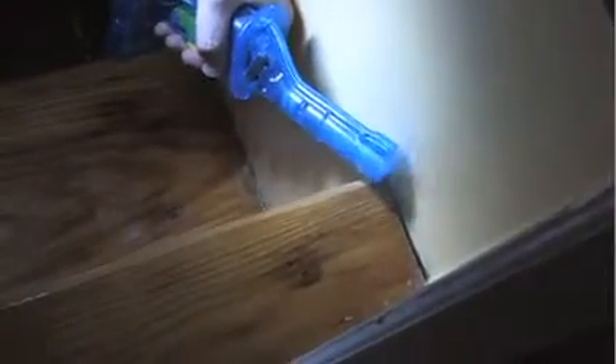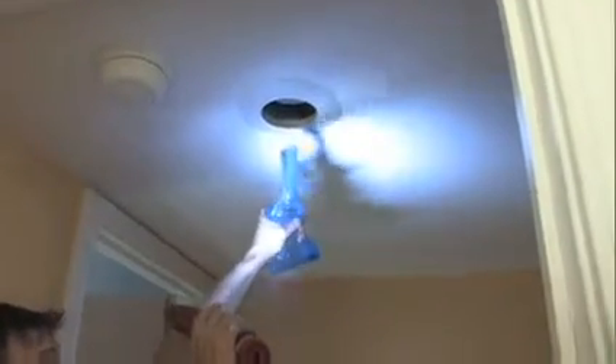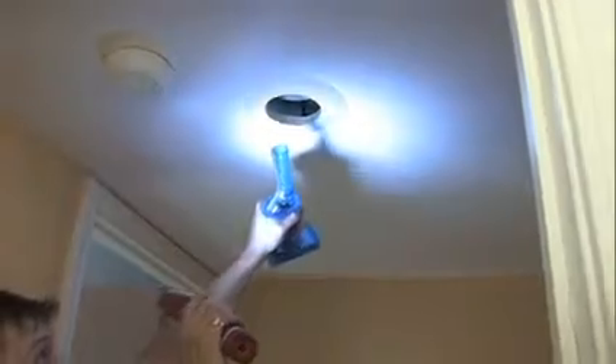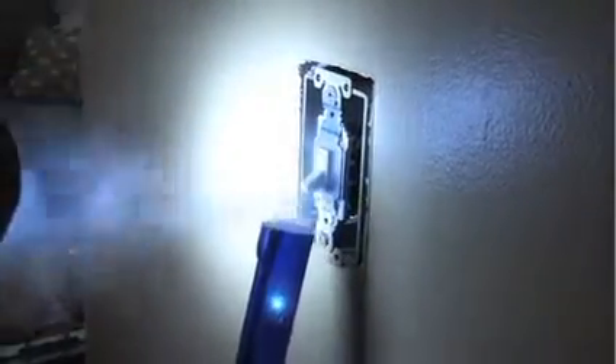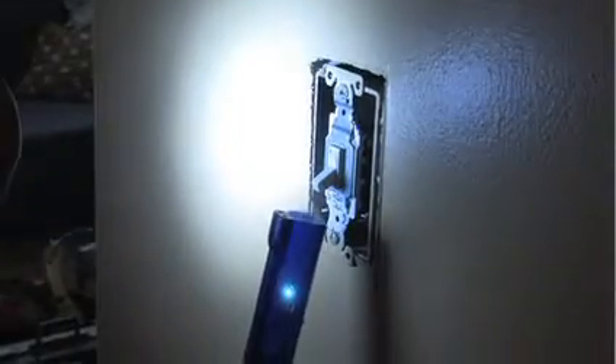The auditor introduces the wizard stick, a smoke generator that looks like a kid's toy, which shows where air is traveling. The majority of air leakage comes from frame cavities — floors, walls, ceilings — not so much the obvious things like windows and doors. Hillary didn't realize all the cavities in the home are so interconnected, meaning wall cavities are more related to pressures outside than pressures inside.